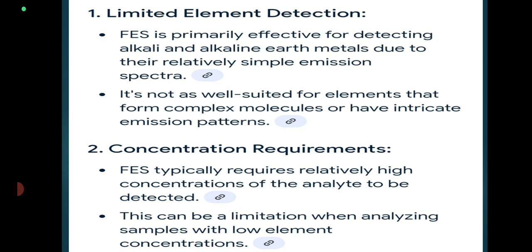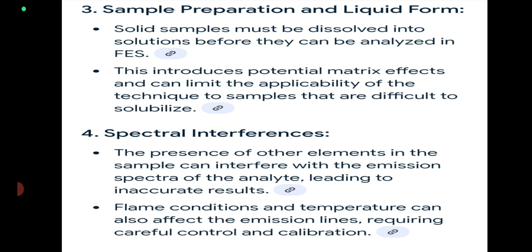Third one, sample preparation in liquid form. Solid samples must be dissolved into solution before they can be analyzed in FES. This introduces potential matrix effects and can limit the applicability of the technique to samples that are difficult to solubilize. Spectral interferences. The presence of other elements in the sample can interfere with the emission spectra of the analyte, leading to inaccurate results. Flame conditions and temperature can also affect the emission lines, requiring careful control and calibration.